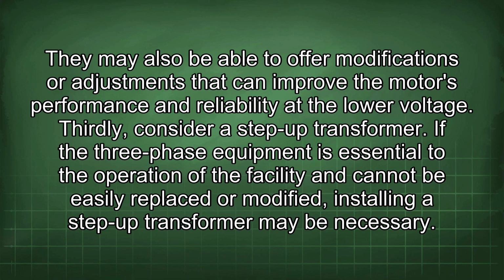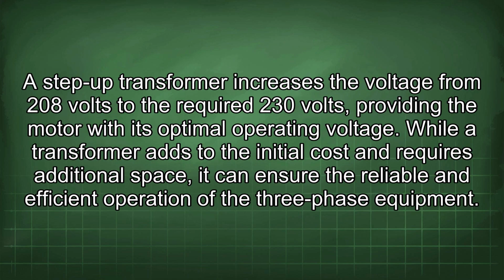Thirdly, consider a step-up transformer. If the three-phase equipment is essential to the operation of the facility and cannot be easily replaced or modified, installing a step-up transformer may be necessary. A step-up transformer increases the voltage from 208 volts to the required 230 volts, providing the motor with its optimal operating voltage. While the transformer adds to the initial cost and requires additional space, it can ensure the reliable and efficient operation of the three-phase equipment.